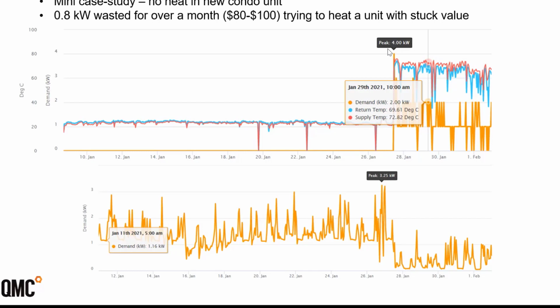As soon as the fan coil manufacturer sent a service person to service that stuck actuator, you see the thermal energy on the top graph, the demand, going back to its usual behavior, and then you start seeing a difference between the supply and return temperatures. When you look at the bottom graph, electricity consumption tracked within the same period of time, it's dropping right after the actuator gets serviced. So this is another great example of what else we can do with the granular meter data we're extracting.